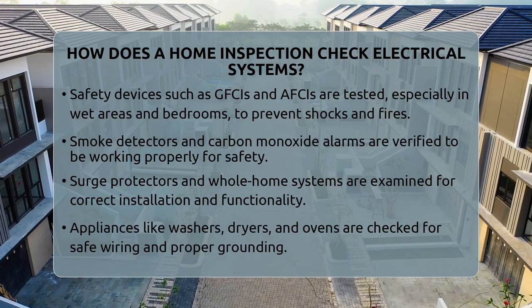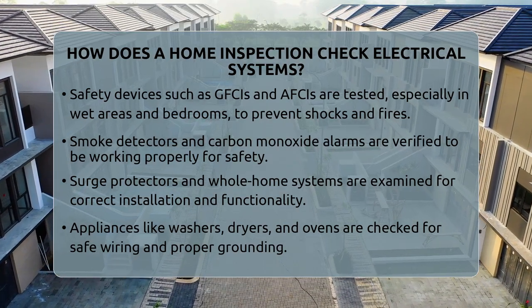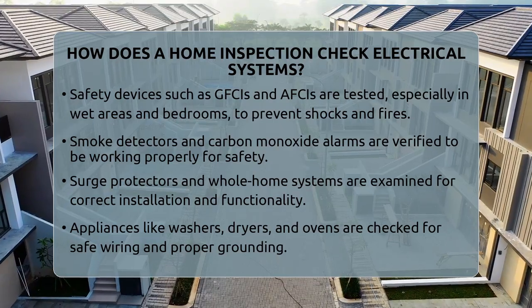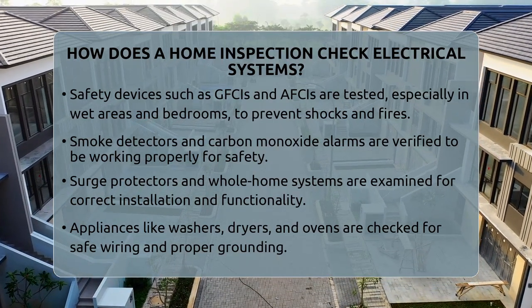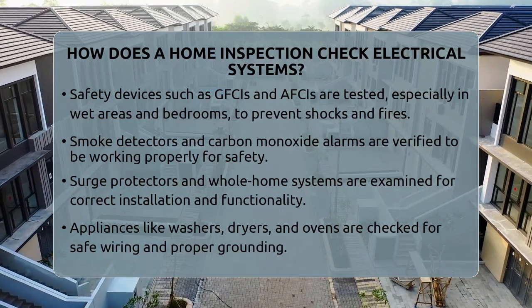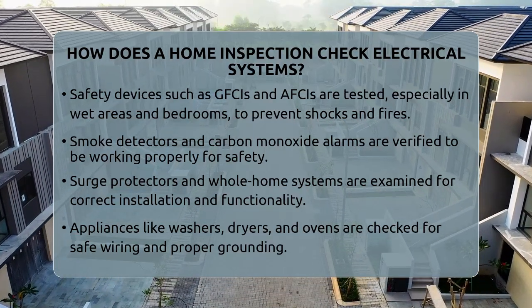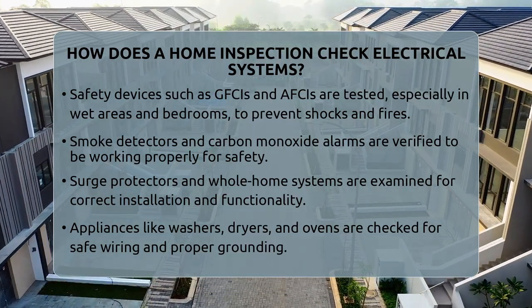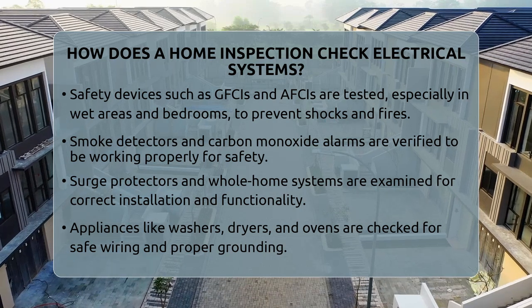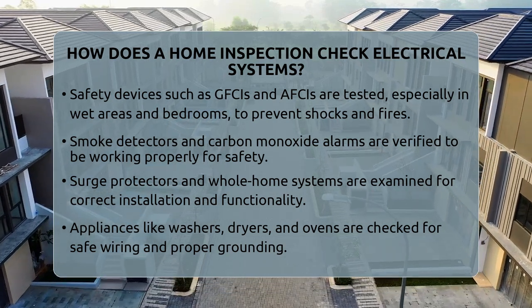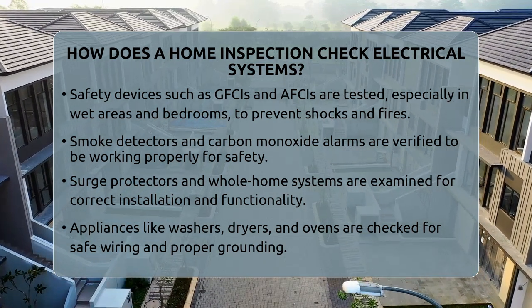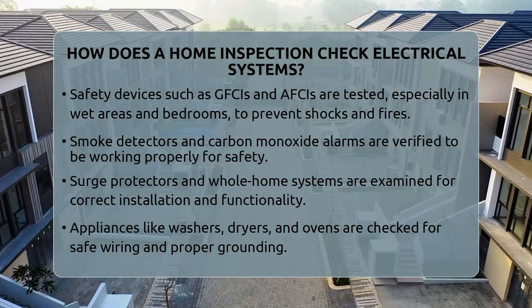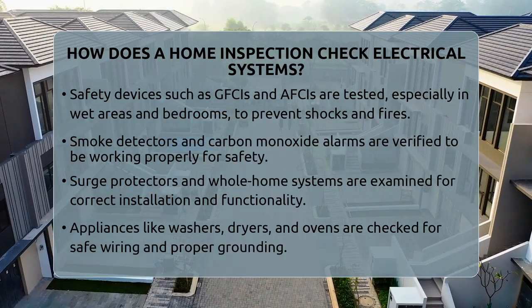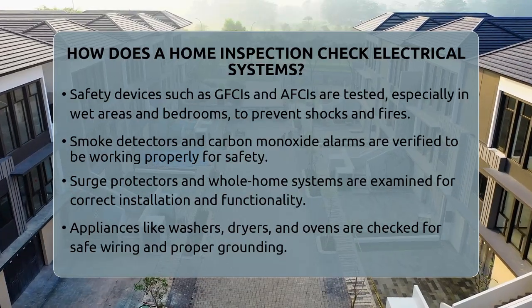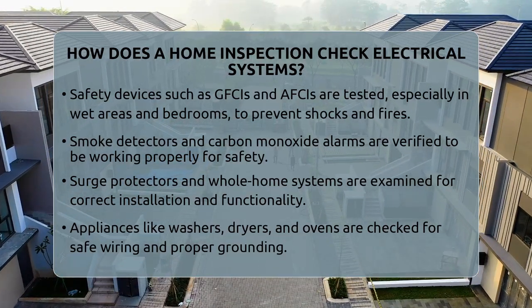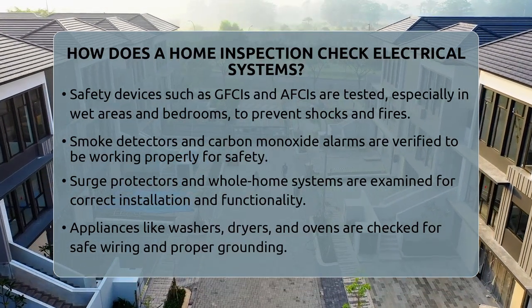Lighting fixtures are inspected to ensure they are securely installed and wired correctly. Bulb wattage is verified to prevent overheating or fire hazards. Safety devices like ground fault circuit interrupters are tested in wet areas such as bathrooms and kitchens. These outlets protect against electrical shocks. Arc fault circuit interrupters are checked in bedrooms and living rooms to prevent fires. Smoke detectors and carbon monoxide alarms are tested to confirm they are working properly.